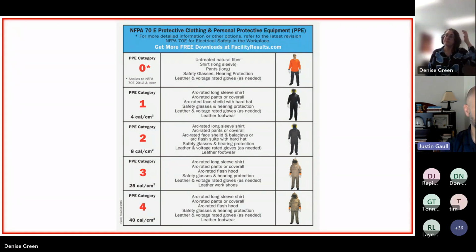Thank you for that. It's not uncommon that we go to a site and we find equipment not well maintained, and you realize that the stickers on there really don't have much value if something's sticky and not tripping on time, or if it's not operating as quickly as it should when you go to operate it. Yeah, you press the button and nothing happens. Who knows what your values actually are? And we see a lot of dirty facilities out there, unfortunately.